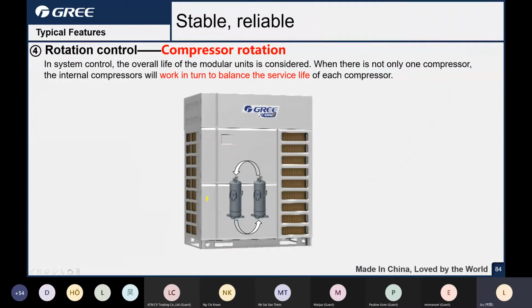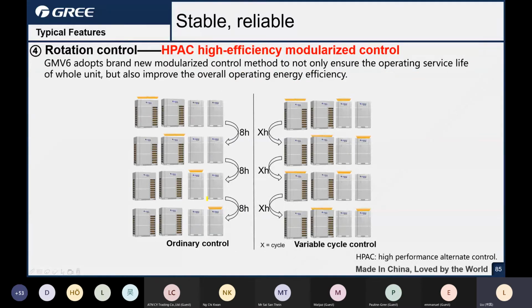Next, reliability technology is about the rotation control of the compressor. If there are two compressors, the units can shift the running sequence and running time to balance the compressor running to get a longer lifespan. And HPAC I already introduced. Depending on the indoor unit capacity, the system will choose the optimal match to make the units run in the highest efficiency region. Do you still remember the curve, right? In the middle. That's the HPAC control.